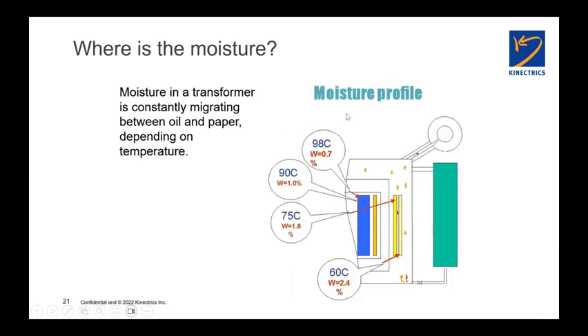Again, just to kind of prove the point, here's a moisture profile inside a transformer. In the middle here, we see the windings. At the top of the winding, where it's operating at 98 degrees centigrade, the water content in this region is only 0.7%. But at the bottom, where it's only operating at 60 degrees centigrade, in this case, an outside winding, the moisture content is much higher. So we need to be very careful when we're talking about moisture content in a transformer. When you're measuring something to determine moisture content, we're always going to be talking about the average moisture content. You need to recognize that there are going to be places in the transformer where the moisture level is higher and places where the moisture content is going to be lower.